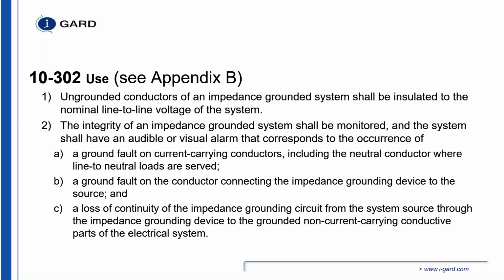But that isn't normally an issue at 600 volts or anything below 5001 volts. It's only really a necessary requirement above 5001 volts, and if you want to maintain your ground fault on the system for greater than 1 hour. For greater than 1 minute, you only need 133% rated cable, but not many systems are going to be high resistance grounding above 5001 volts.